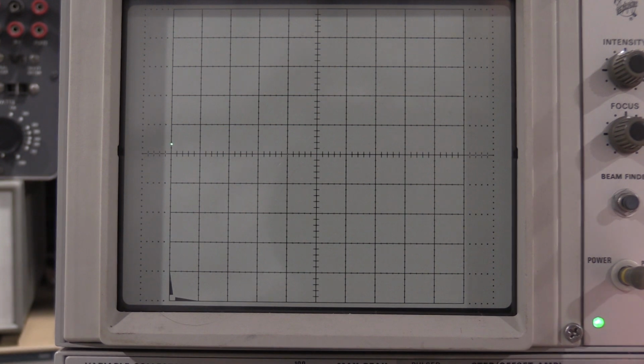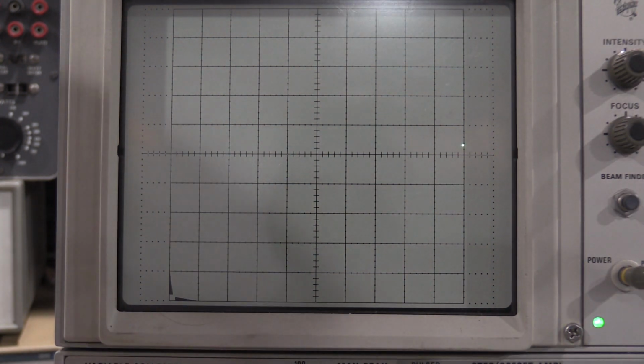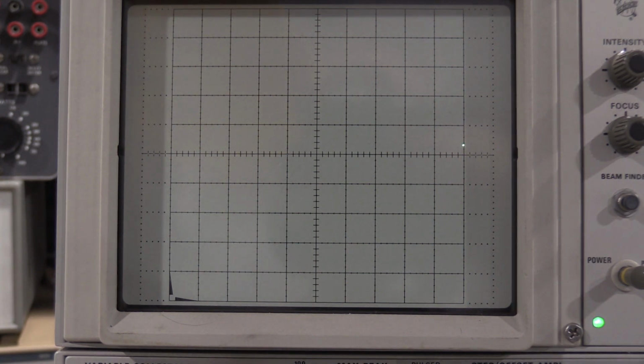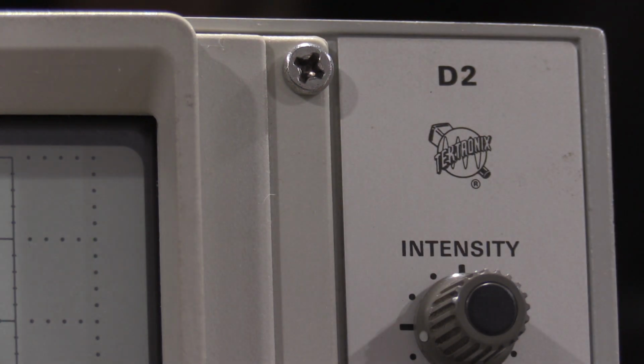So what we're going to do is wind that up to 502 millivolts. So there we go, and it is supposed to be within 0.05 divisions of the right 10th graticule line. We're right on the line. I'll zoom in here real quick. See if we can get some focus. So we're right on the line, so the horizontal amplifier gain's fine, does not need adjustment. The next step, which is 12, is adjusting the sensitivity correction. It's D1 only. We're working on a D2, so we get to skip that step.